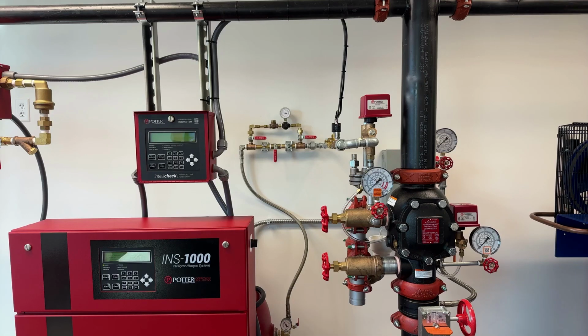The AAMD is installed between an air or nitrogen supply, which typically operates at a higher pressure than the pressure needed for the system to properly operate, and the dry or pre-action sprinkler system. The AAMD must be installed in the proper orientation, with the sprinkler system being downstream of the regulator and the nitrogen or air supply upstream of the regulator. Remember that each sprinkler system must have a dependable nitrogen or air supply capable of filling the system within 30 minutes in accordance with NFPA standards.